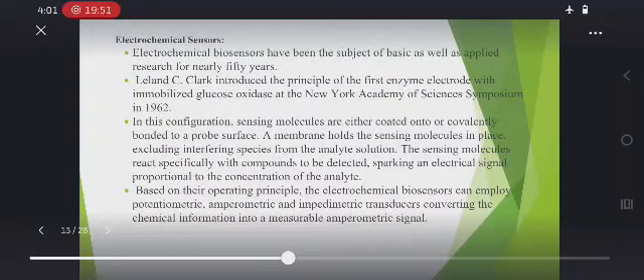In this configuration, sensing molecules are either coated onto or covalently bonded to a probe surface. A membrane holds the sensing molecules in place, excluding interfering species from the analyte solution. The sensing molecules react specifically with the compounds to be detected, producing an electrical signal proportional to the concentration of the analyte. The analyte can be microorganisms, DNA or enzymes.